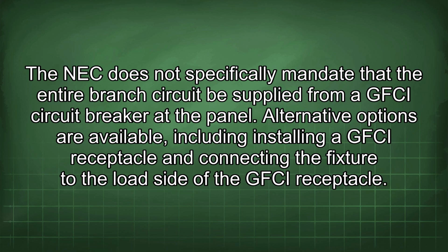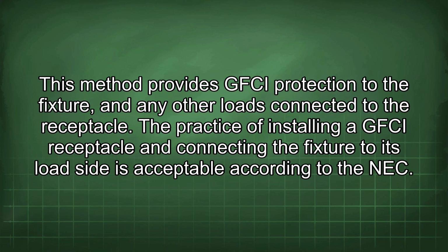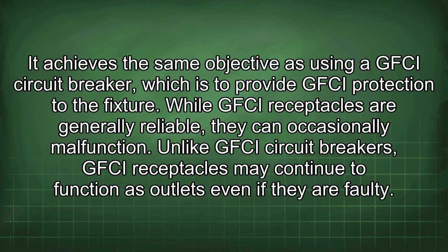The NEC does not specifically mandate that the entire branch circuit be supplied from a GFCI circuit breaker at the panel. Alternative options are available, including installing a GFCI receptacle and connecting the fixture to the load side of the GFCI receptacle. This method provides GFCI protection to the fixture and any other loads connected to the receptacle. The practice of installing a GFCI receptacle and connecting the fixture to its load side is acceptable according to the NEC.